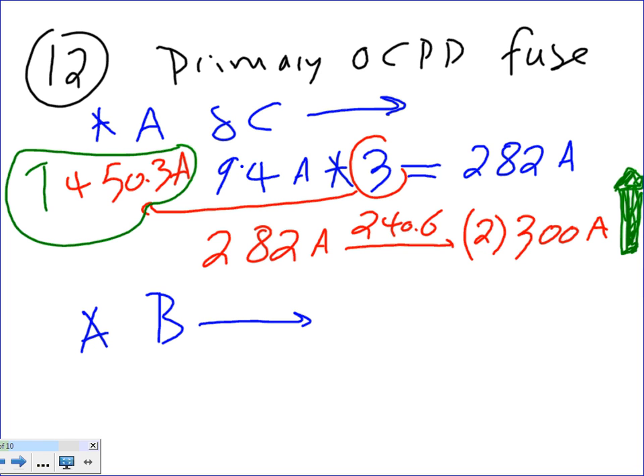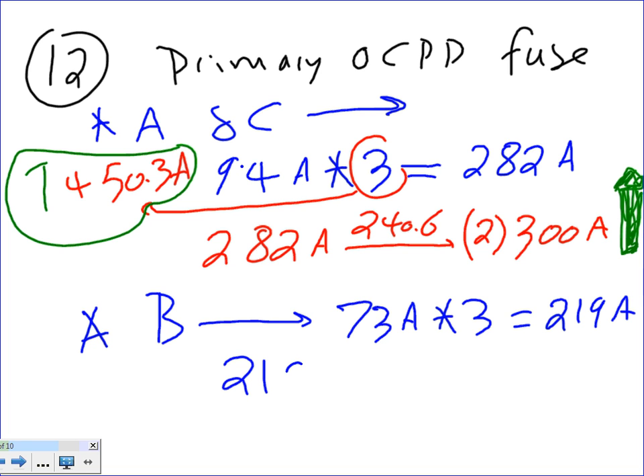The primary B phase was 73 amps. Multiply this by the same thing, 3. Multiply 73 by 3, you end up with 219 amps. Take the 219 amps to 240.6, and this will give you the next standard, which is 225 amp. How many fuses? 1 fuse.